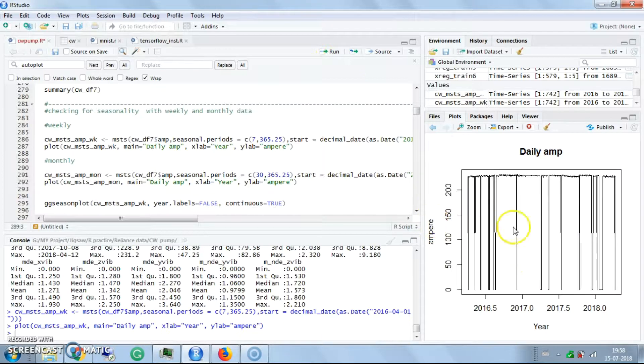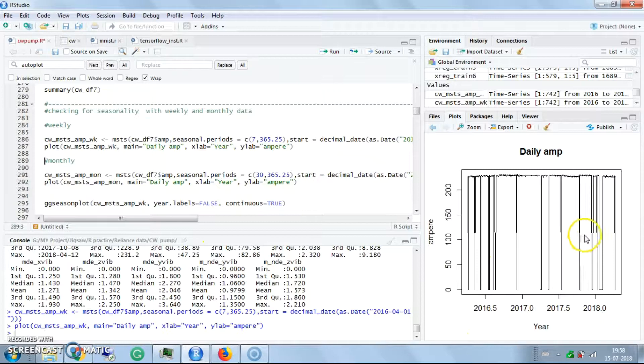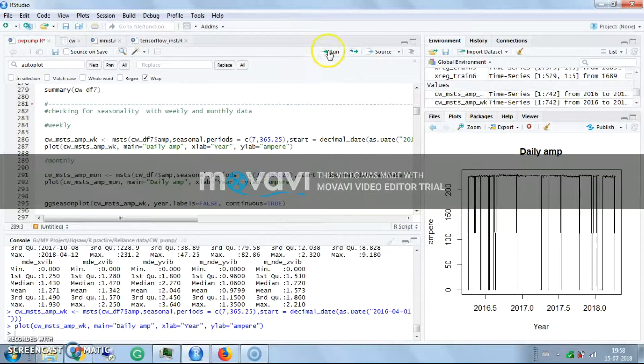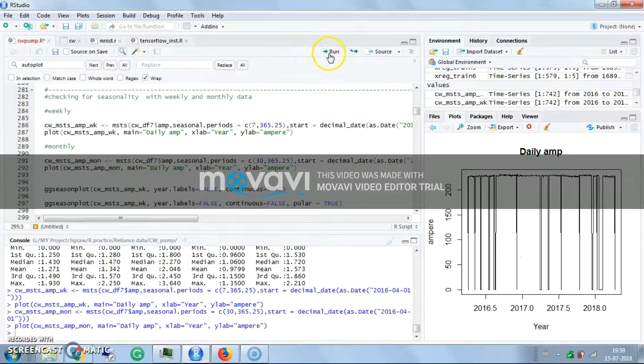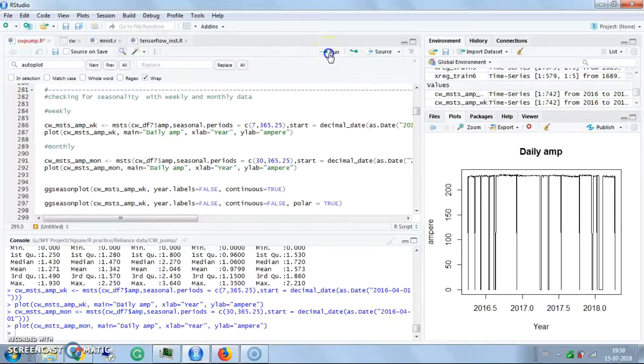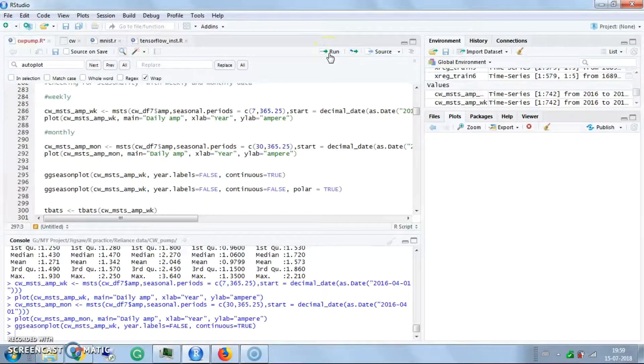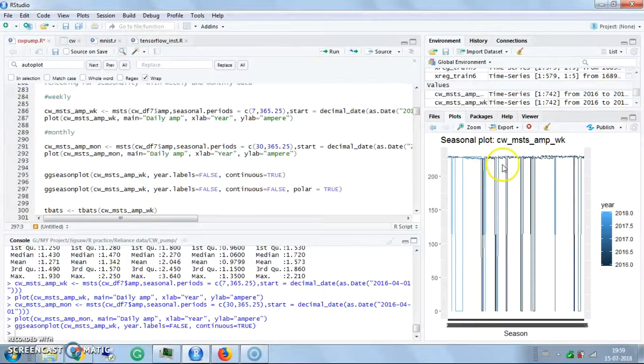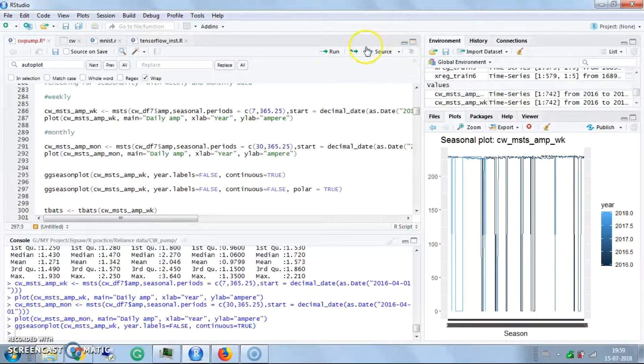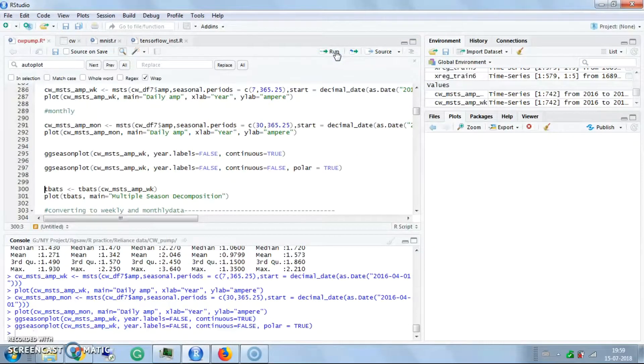For weekly and monthly, I want to see how the pump runs weekly and monthly in the daily amperes. Over the years it shows a downtrend because when the pump remains in stop condition it's zero value, so it shows downtrends in monthly data.